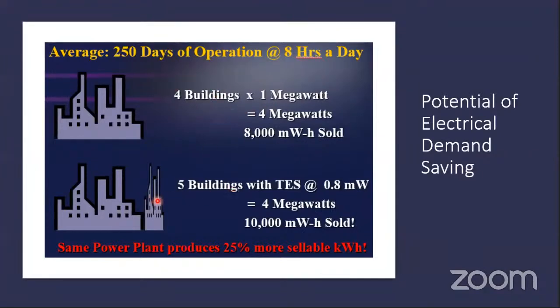However, if there was a provision for thermal energy storage, let's say in all these buildings, then it was possible to reduce the connected load, let's say down to 0.8 megawatt, and the same power plant could produce 25% more sellable kilowatt hours, as well as the electrical load could be connected to five buildings instead of four. So you see, the sellable megawatt hour has now increased with the same amount of power plant. So in a way, we are also reducing the requirement to produce more power plants.